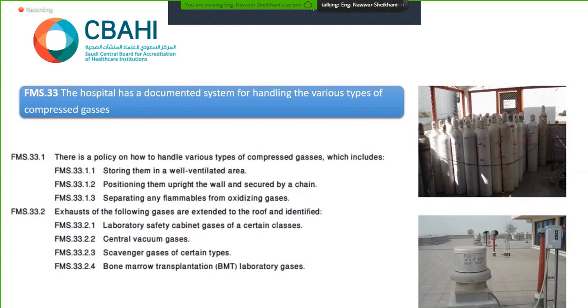We have to check the exhaust for the laboratory safety cabinet, for central vacuum gases, for the scavenging system, and for the BMT laboratory gases. Usually, this exhaust should be located on the rooftop. The height of this exhaust should be a minimum of 2.5 to 3 meters above the floor level of the roof, and be at least 25 feet or 8 meters away from the fresh air supply of the AC.